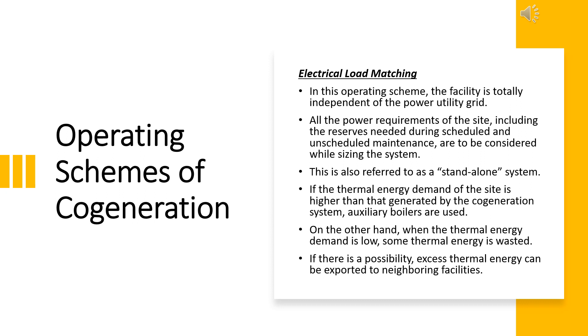When the thermal energy demand of the site is higher than what is generated by the co-generation system, auxiliary boilers are used. On the other hand, when the thermal energy demand is low, some thermal energy is wasted. If there is a possibility, excess thermal energy can be exported to a neighboring facility.